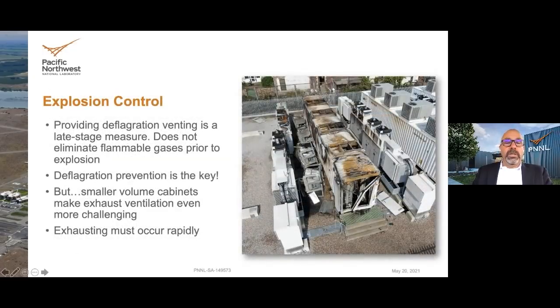When you provide deflagration venting, the blowout panel is a late stage measure. The explosion has already occurred, so it doesn't eliminate the flammable gases prior to the explosion. We really feel that preventing an explosion is the key. As these systems move more towards a cabinet design, accessed from the exterior with more batteries inside, there's even less free air volume to ventilate. It's going to become even more challenging, and it has to happen more rapidly.